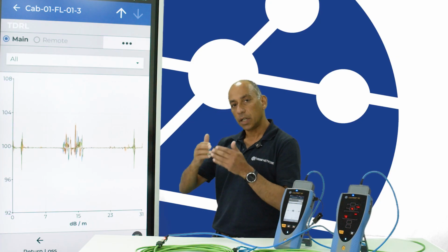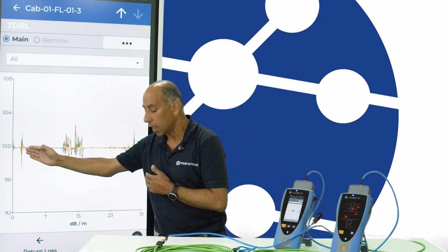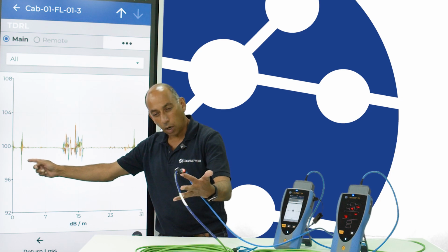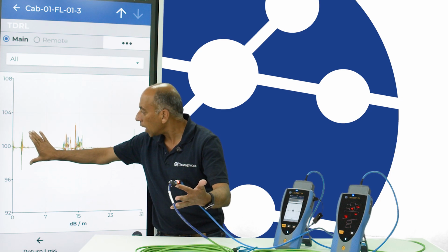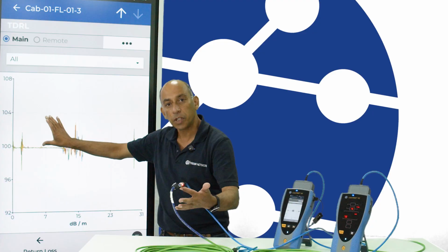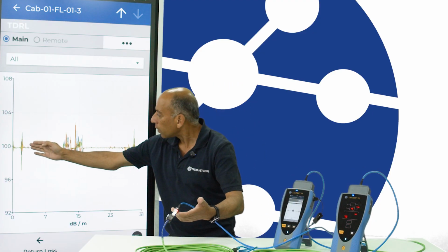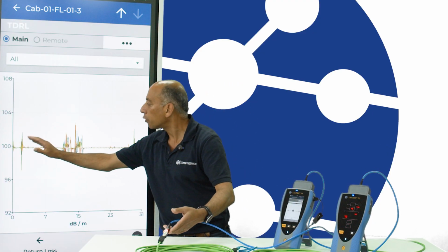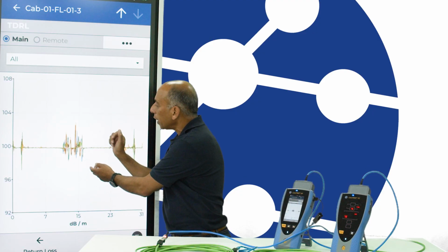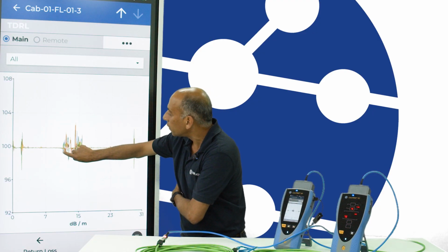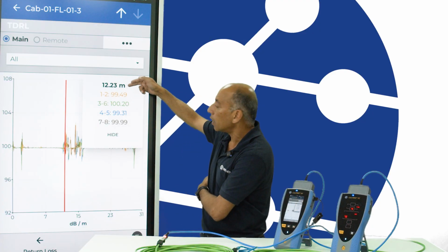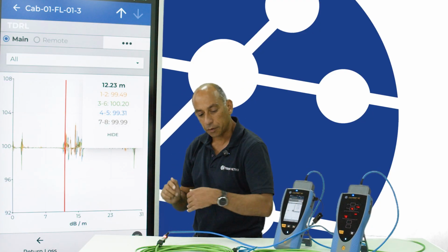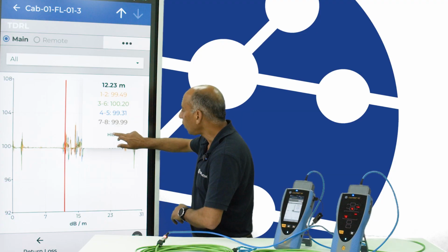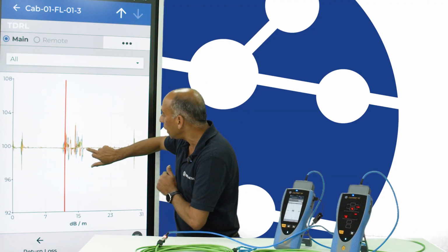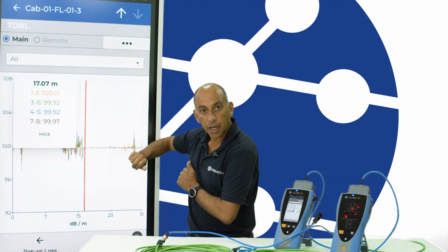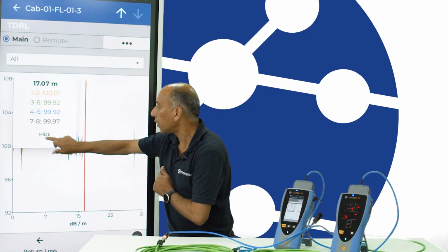And so what we'll see is a pulse put into the cable at the start. This first point is representative of our first connection, and the amplitude there is less than 4 dBs, saying it's a fine connection. I can look across and see some energy reflected back. As these reflections are reflected back, we can even touch the screen anywhere, and we can see at roughly 12 meters, we have something. There's our problem connection. I'm going to hide that to show you, once again, you can touch the screen anywhere to get the indication of that problem length, okay?